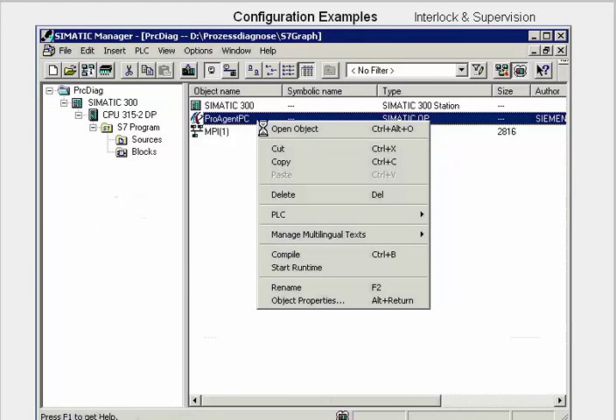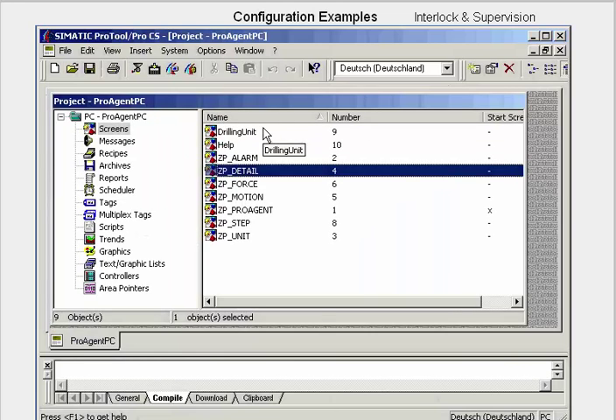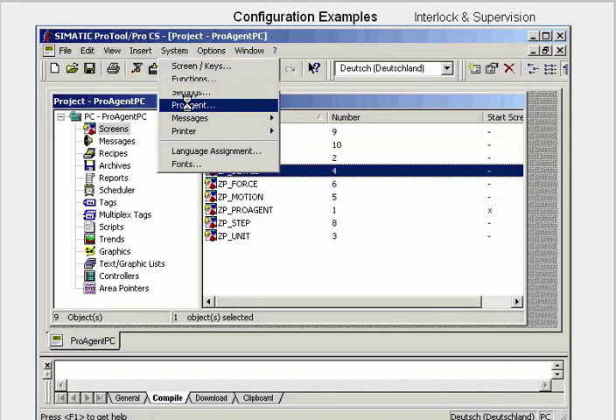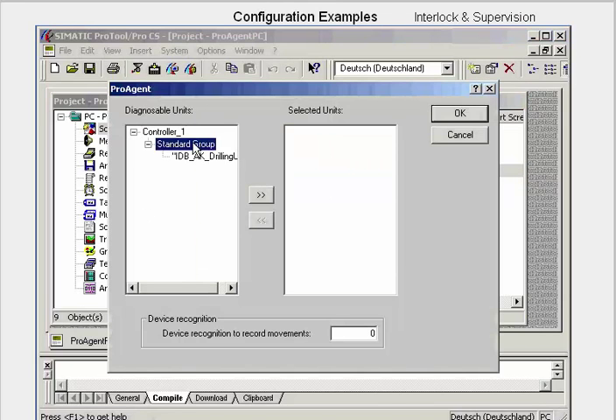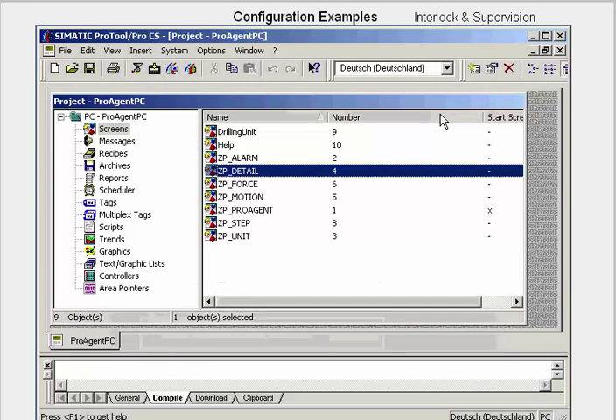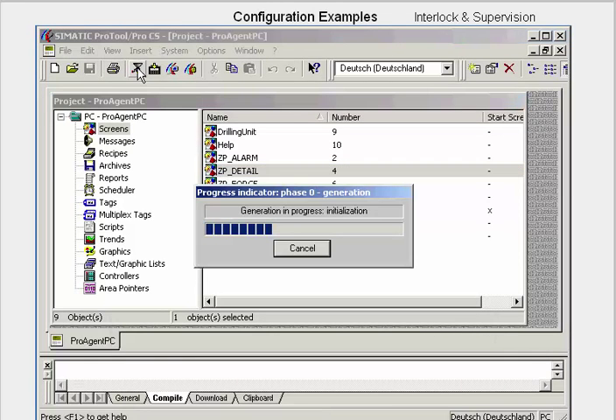Now we open the ProTool application. In order to be able to configure with ProAgent, we go to the menu item System and open the dialog ProAgent. In the standard group, we select the unit that supports diagnostics and transfer it to the selected units window. We close the dialog with OK, save the project, activate generation, and then start the runtime.